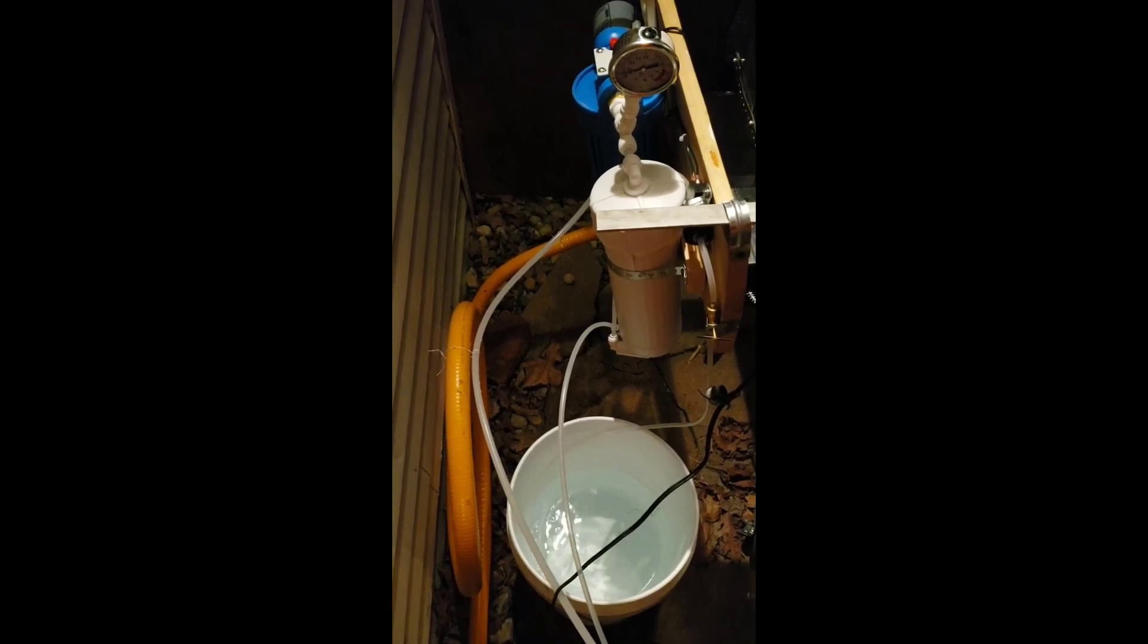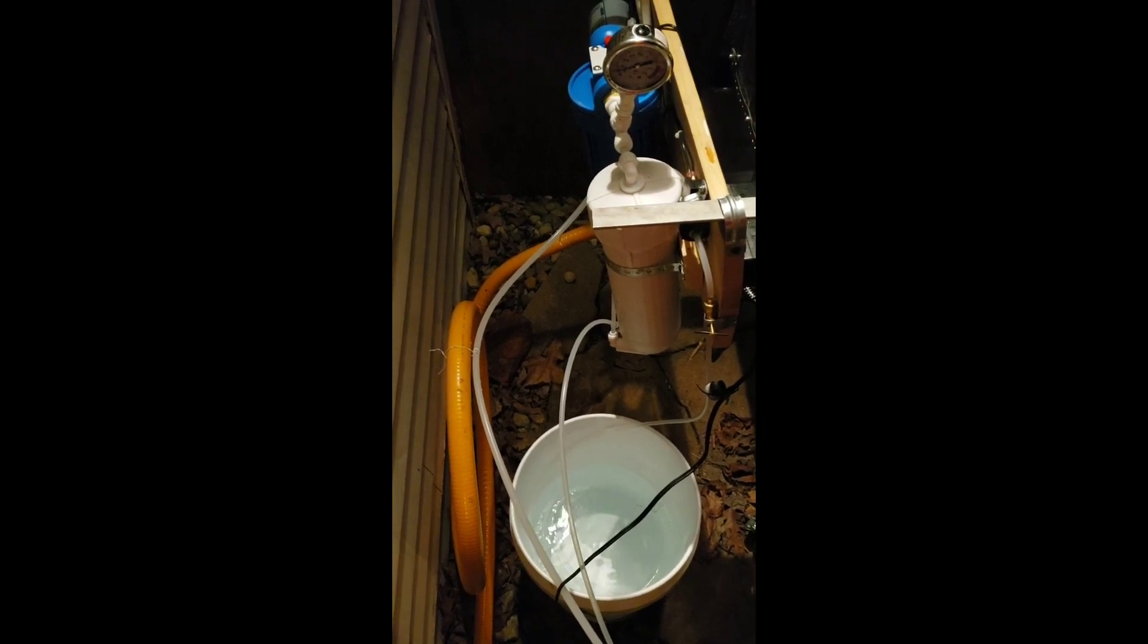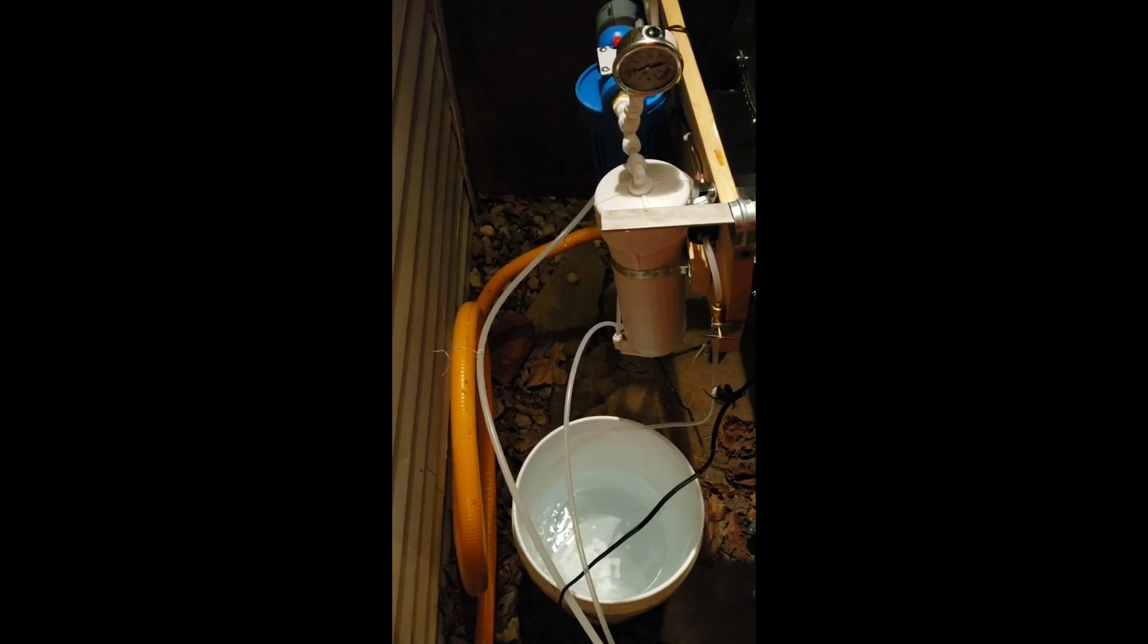We're going to keep that needle valve all the way open and we're going to run about 10 gallons of fresh permeate through the filter and the RO to rinse that sugar and anything else off of that membrane and keep it pretty clean.